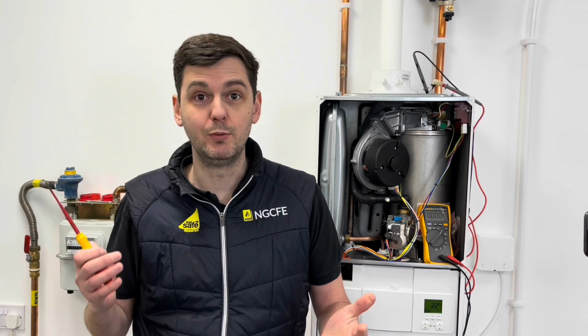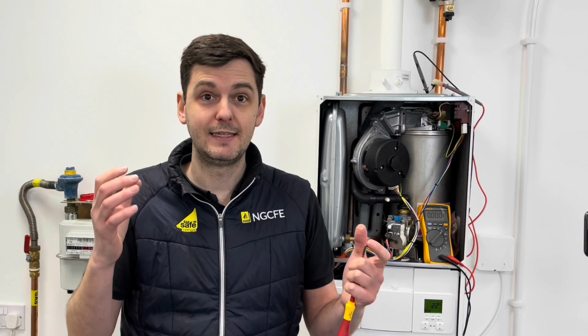If for whatever reason we were to have a low reading, that would indicate that for some reason the flame's finding it difficult to conduct the voltage AC and convert it through to DC. That could be that it's a vitiated flame, it's a poor flame. It could be that someone set the minimum setting wrong on the gas valve. So when it's modulating down, it's losing the ability to conduct that voltage AC and convert the voltage through the flame.